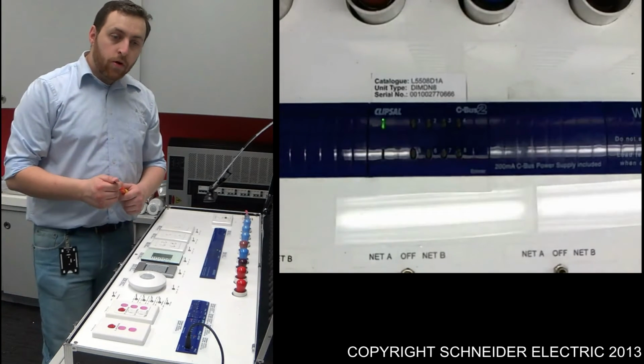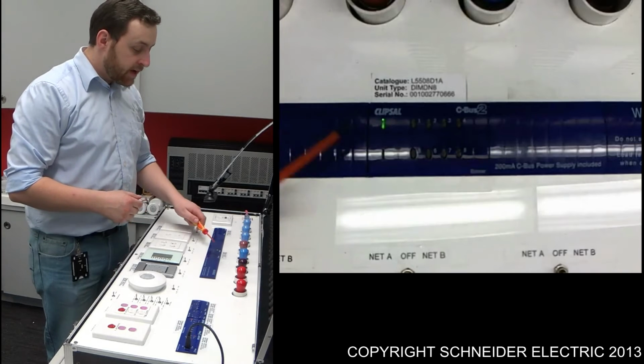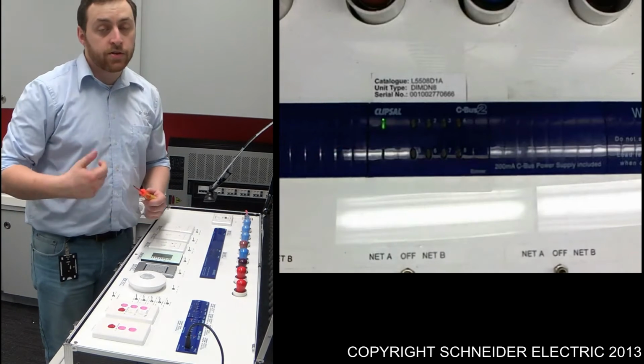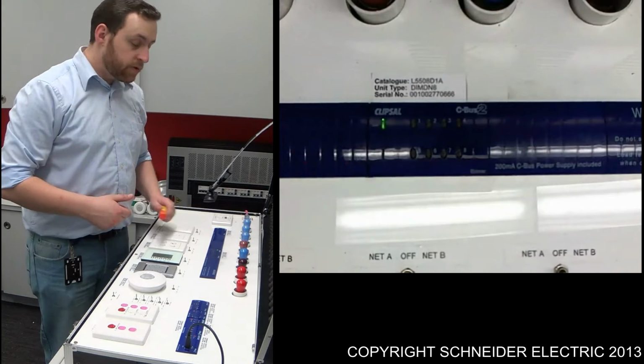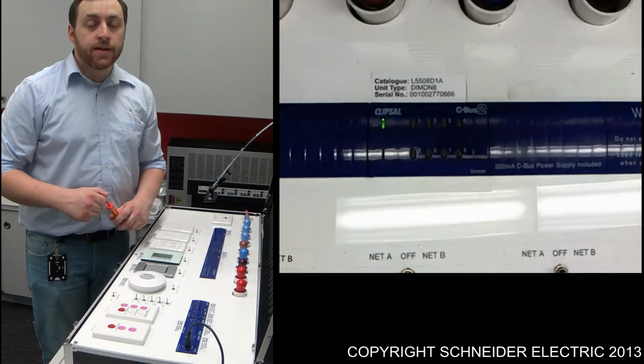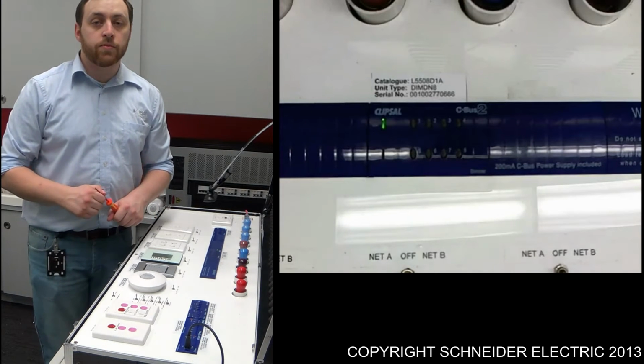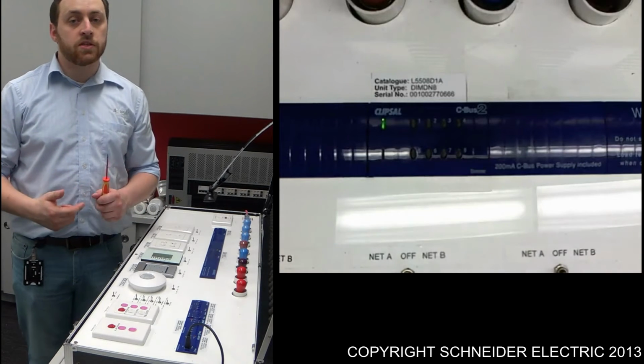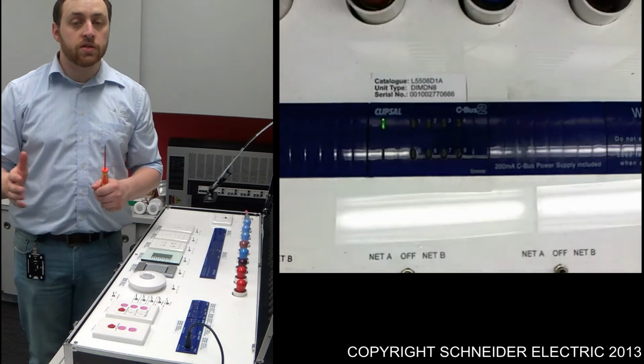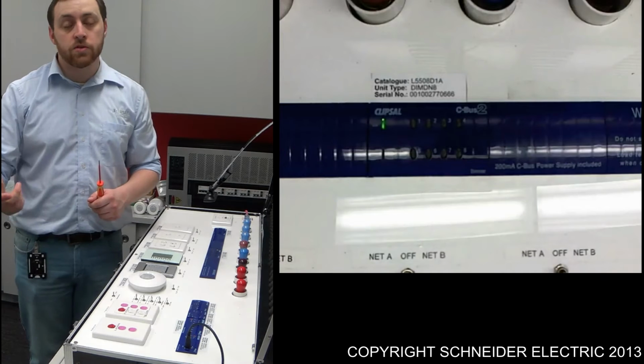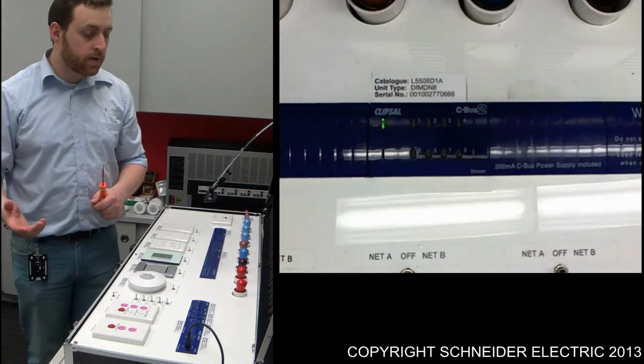Now, what we've got on my training board right now is an 8-channel dimmer with its unit light, or unit LED, on solid. However, its CBus LED is actually off. Now that's a bad thing for a CBus network, because basically it means there's no CBus communications happening across the network. So that means switches aren't talking to your dimmers and relays and so on and so forth.